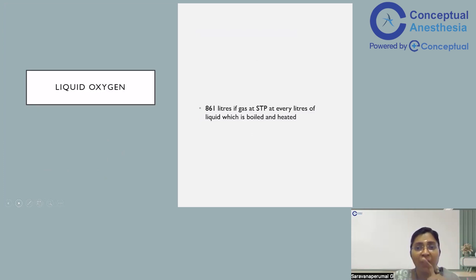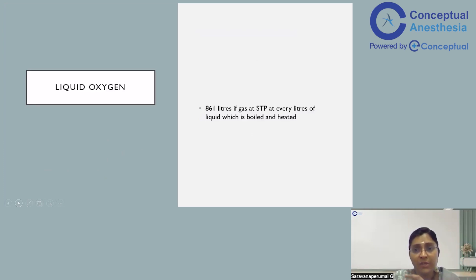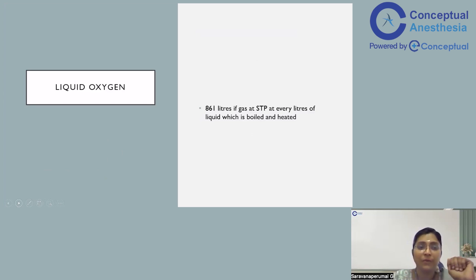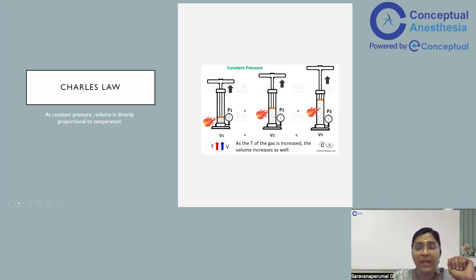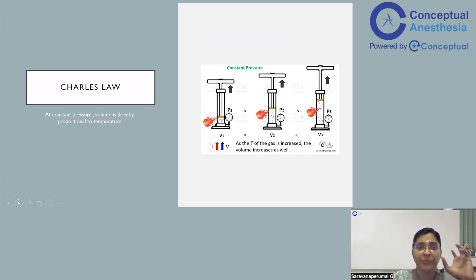One should always remember that a liquid oxygen plant is used for extracting larger amounts of oxygen. Approximately 861 litres of gas can be extracted from every litre of liquid oxygen when boiled and heated to the appropriate temperature.